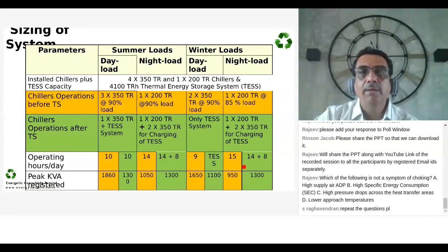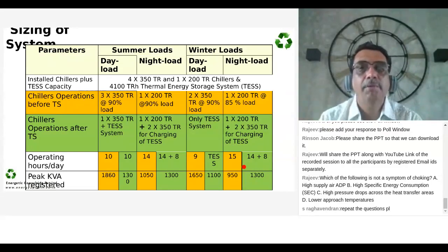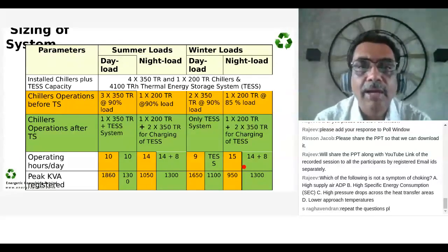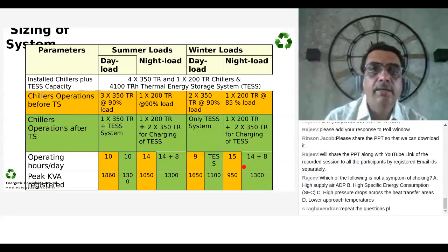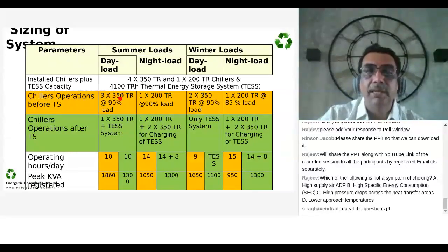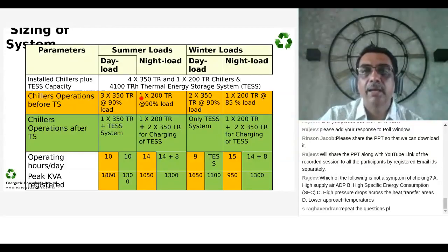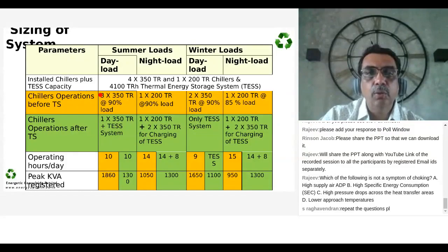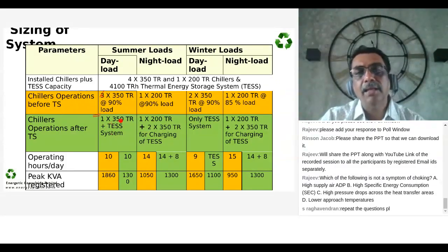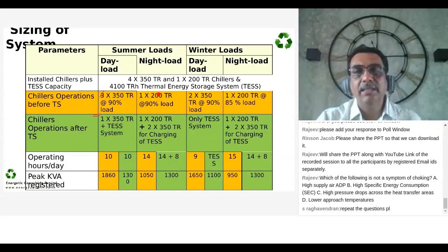Now, this was the scenario. Perfect. When we had a summer load, we had a day load and a night load, if you could see. During the day, 3 chillers of 350 TR, that is operating at 90%, and 1 chiller of 200 TR operating at 90%. After the thermal storage implementation, only 1 chiller. So instead of 3, I could switch off 2 chillers, right? And the thermal storage started to discharge. This continued to operate the way it is.